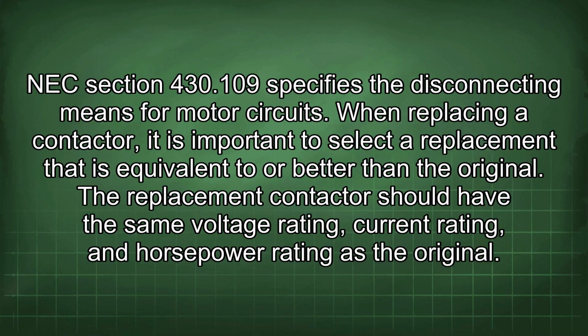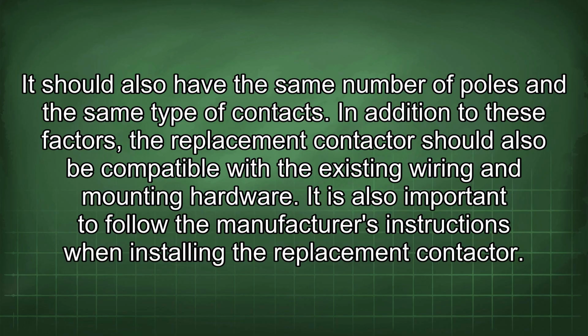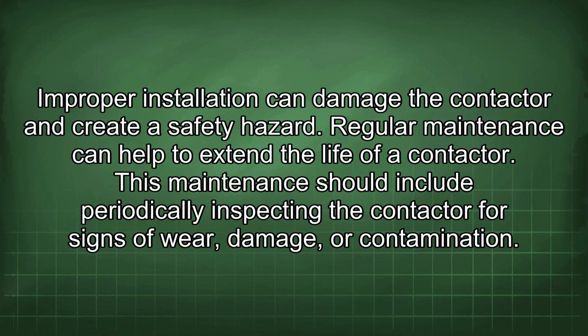When replacing a contactor, it is important to select a replacement that is equivalent to or better than the original. The replacement contactor should have the same voltage rating, current rating, and horsepower rating as the original. It should also have the same number of poles and the same type of contacts. In addition to these factors, the replacement contactor should also be compatible with the existing wiring and mounting hardware. It is also important to follow the manufacturer's instructions when installing the replacement contactor. Improper installation can damage the contactor and create a safety hazard.